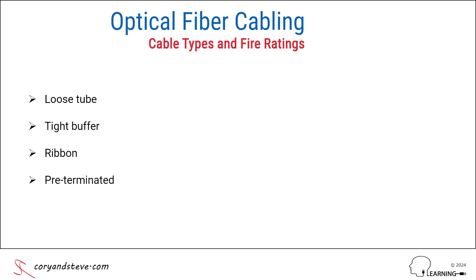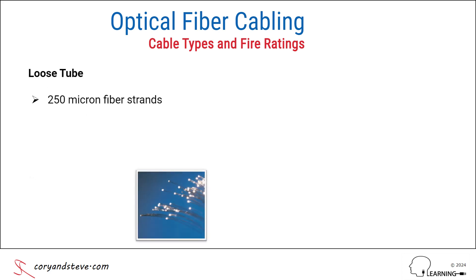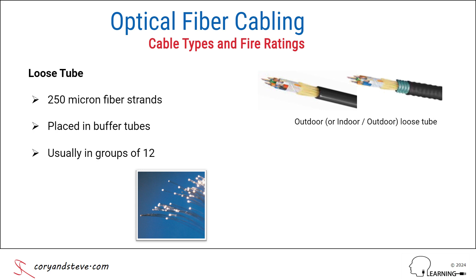The first type of cable construction is loose tube, where 250 micron fiber strands are placed in buffer tubes within the cable, usually in groups of 12. This construction is routinely selected for aerial or underground outdoor cables used to interconnect multiple buildings on a campus, with gel or tape used to prevent moisture infiltration. If necessary, additional physical protection can be provided by one or more layers of corrugated steel armor between layers of jacketing.